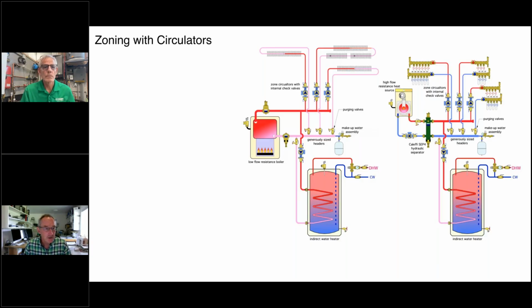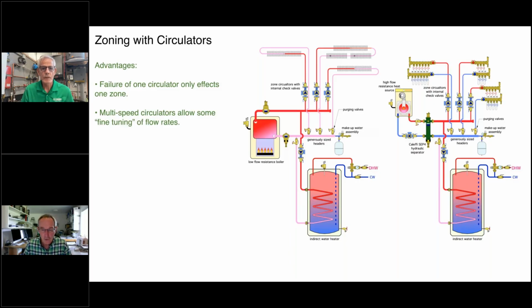So, advantages. Failure of one circulator only affects one zone. So if one of the baseboard zones has a circulator failure, which can happen, but quite honestly, it's relatively rare in a well-designed, well-maintained system, only that zone would be affected. And today, most of the zone circulators have multiple speed settings. So based on doing flow rate and head loss calculations and comparing those results to pump curves, you can reduce energy input to the system, electrical energy input, by adjusting the speed of the circulator. So those are a couple advantages.